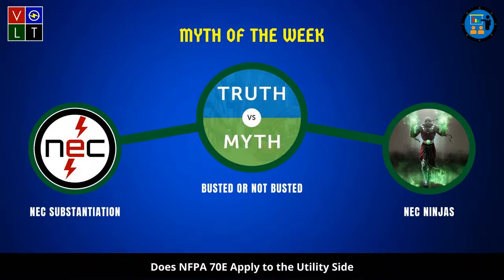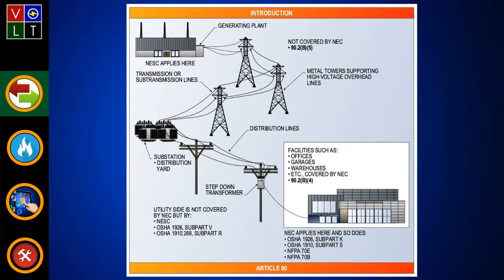There's a couple things to look at. When it comes to 70E, a lot of people get confused between NFPA 70E and IEEE 1584. 70E is a consensus standard we use for developing requirements for people that are exposed and how we protect them. 1584 is where we go to get the information needed to calculate the hazard and determine the incident energy. That's where some of the confusion comes from.